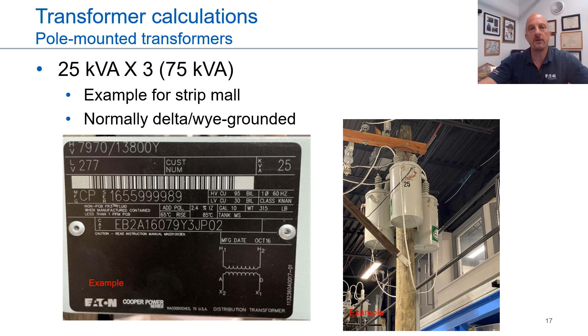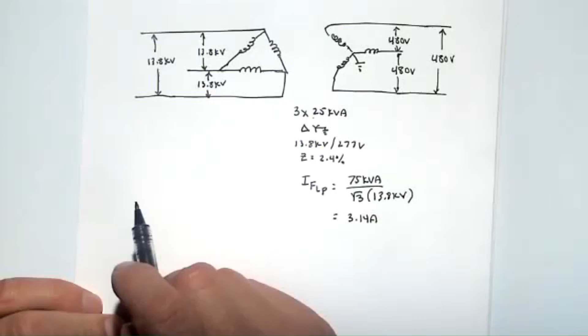Okay, now that we're getting pretty comfortable with these calculations, we're going to throw another little wrench in the plans. We're going to say there's 3 single-phase transformers pole-mounted, and those transformers are connected in delta Y, as shown here. So this winding corresponds to that one, this one to this one, and this one to that one. Each transformer is rated 13.8 kV line to line, 277 volt line to neutral. So here's our neutral point on the secondary of the transformers. 480 volt line to line on the secondary.